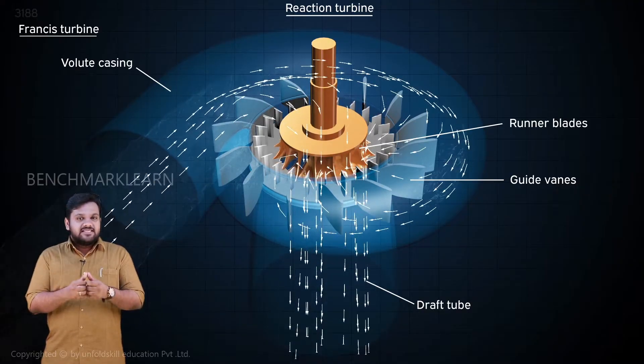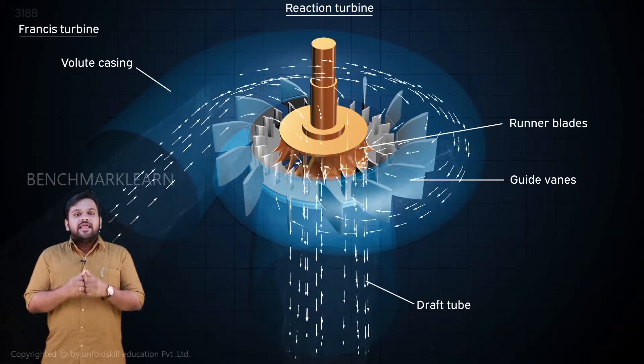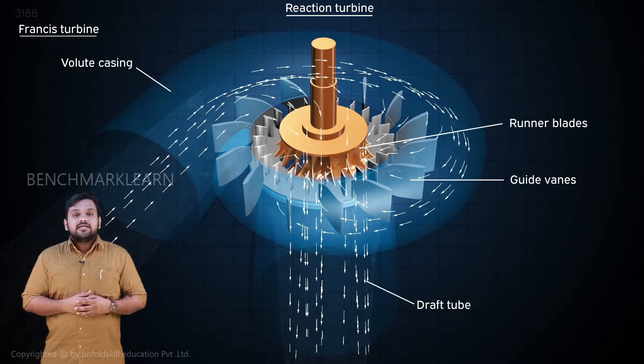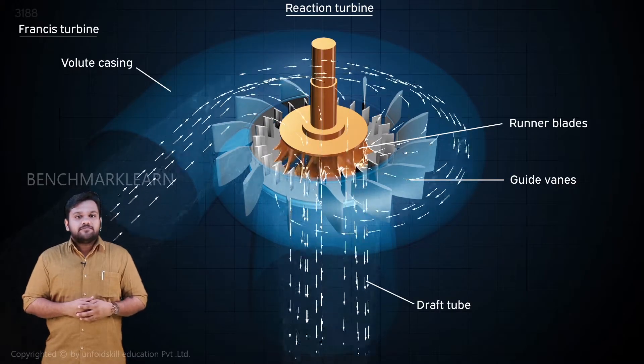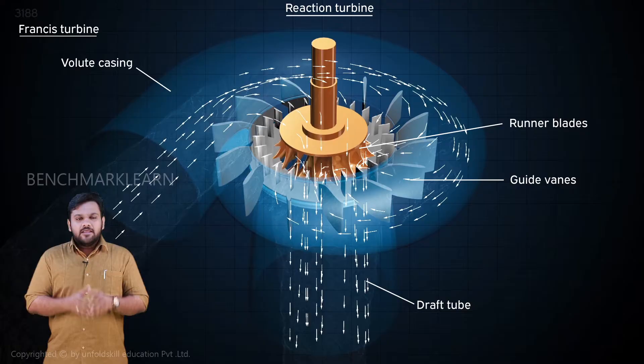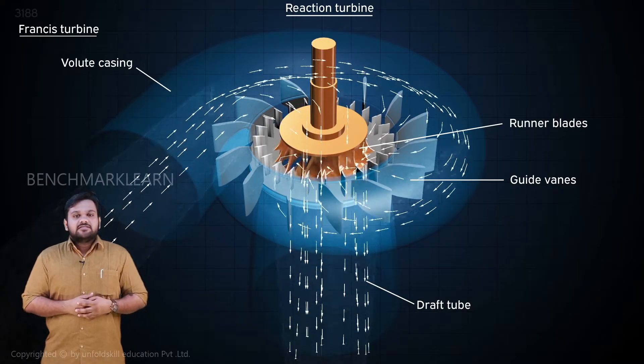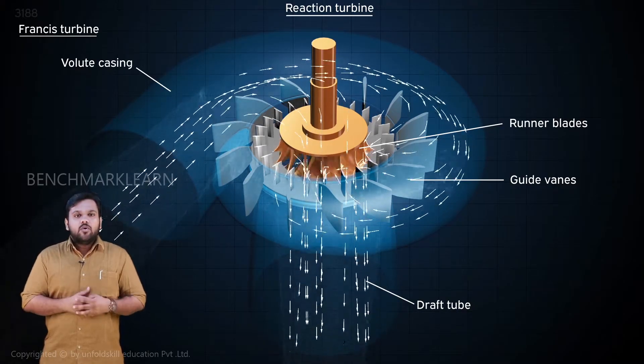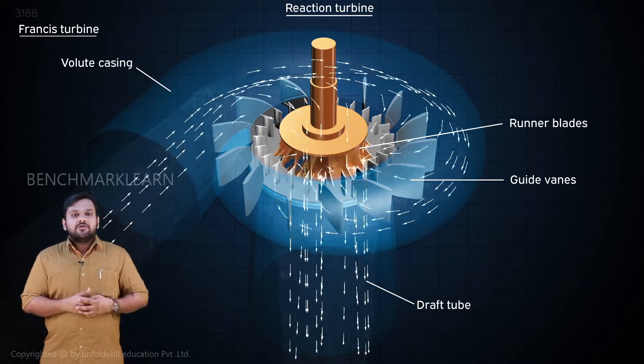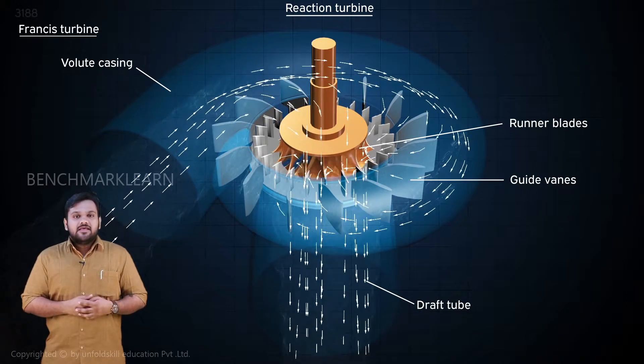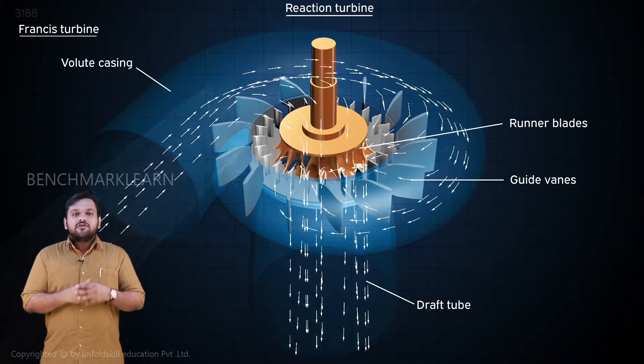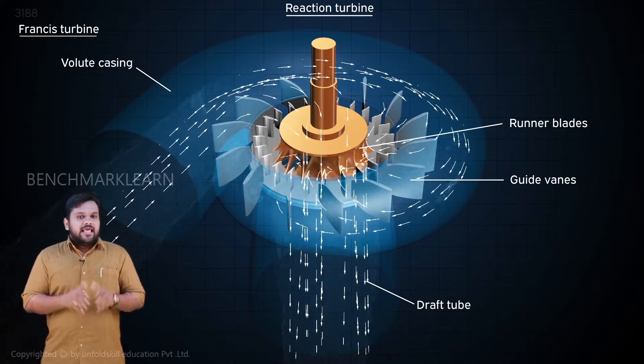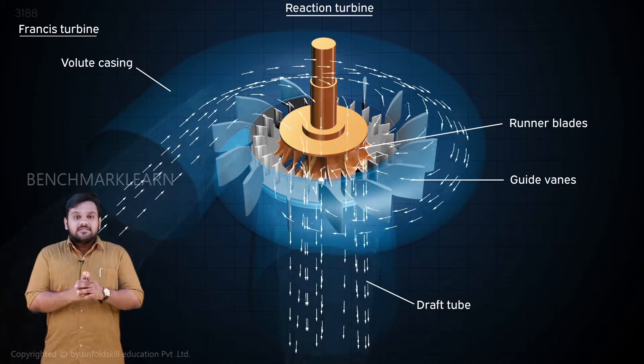It is the net pressure difference from the inlet to the outlet which determines the energy from the turbine. To achieve a maximum difference, the outlet pressure is kept very low, sometimes less than atmospheric. This will prevent the natural flow of water from the outlet. A draft tube corrects this.